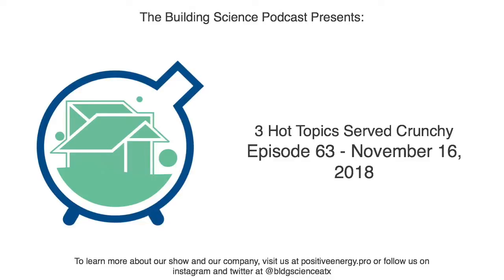That is awesome. I mean, that's really astounding. And it also speaks to me to the velocity, the feet per minute. Do you know your feet per minute across that filter, or roughly? I think that's probably in the 150 to 200 feet per minute ballpark. And so the pressure drop across that filter is around 0.04 inches of water. And that's fascinating to hear that it's around 0.04, whether it's a MERV 2 or a MERV 13.